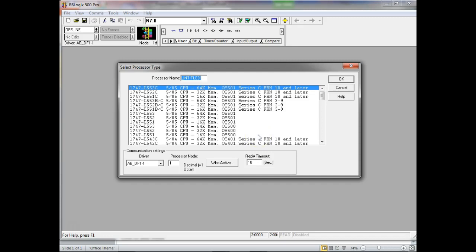So when y'all say select the CPU, that's only if you're what? Creating a new program. Because it's got to load in the right compiler. It's got to load in the compiler for this PLC. This PLC speaks machine language. I'm programming in a high-level language, so we got to have a compiler, which is that program that takes a high-level language program and converts it into the binary language for the PLC. So that's basically one of the things that we're doing here, plus establishing inputs and outputs.